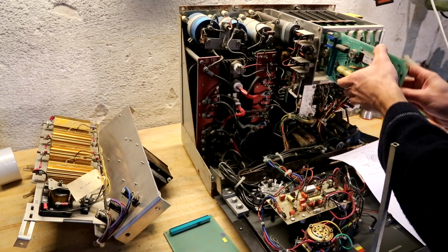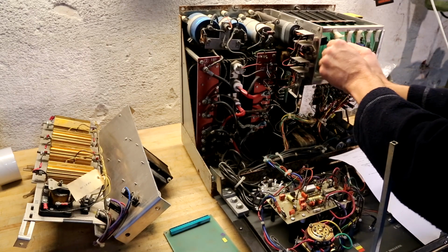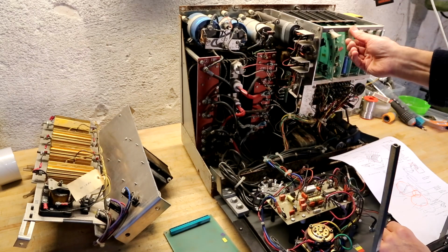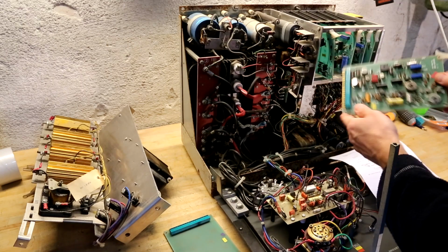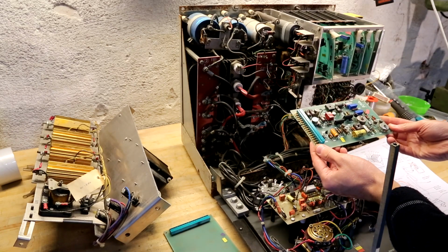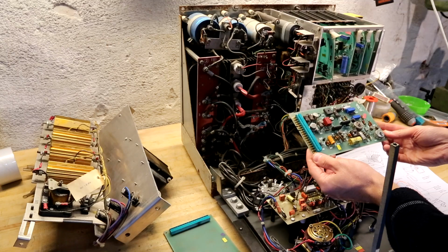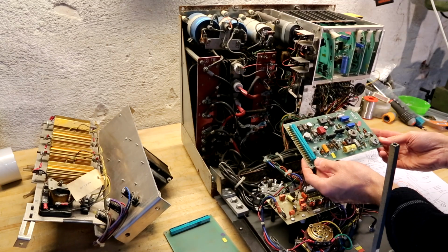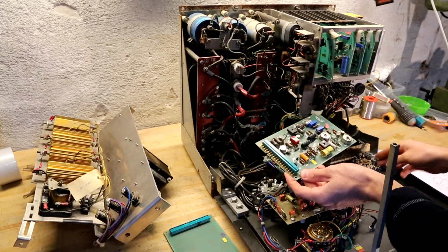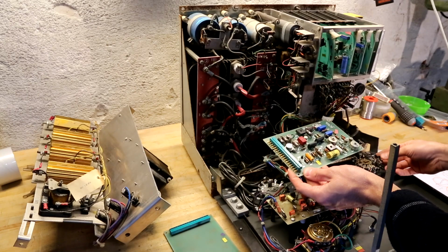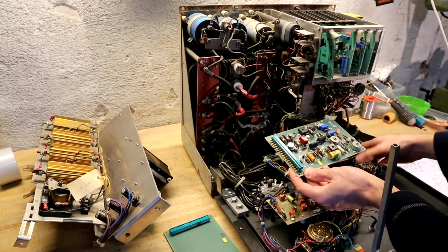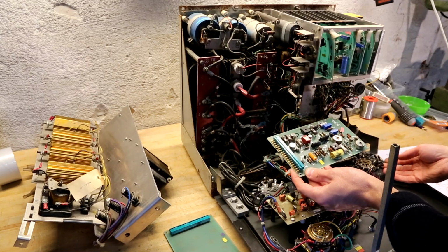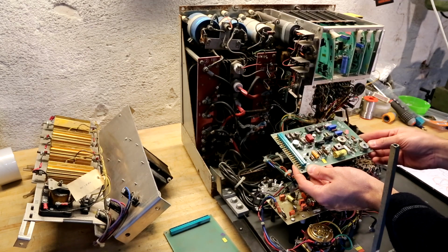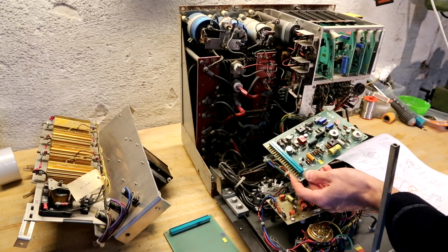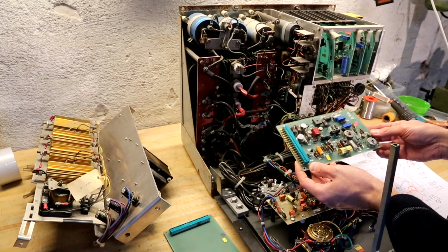Then there is card 2. Here it says the filament and milliampere regulator. So this drives the filament supply and also the regulation from the front selector switch here, which actually just is a series connection of resistors. So depending on this resistance, this board determines the current that is driven out into the X-ray tube.